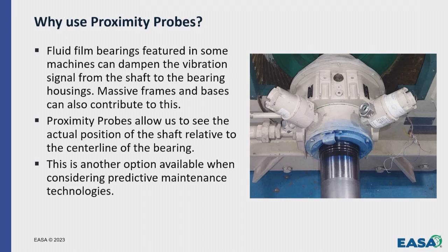So when we have these machines, these are typically larger machines. They're going to be on big bases, typically large foundations or large frames. And so all that damping in the frame and the base can give you a false indication that your vibration levels are better than they are. So your case may say that everything's nice and smooth, but your rotor is actually using up most of the available space in the bearing, causing additional heating and shortening the life.